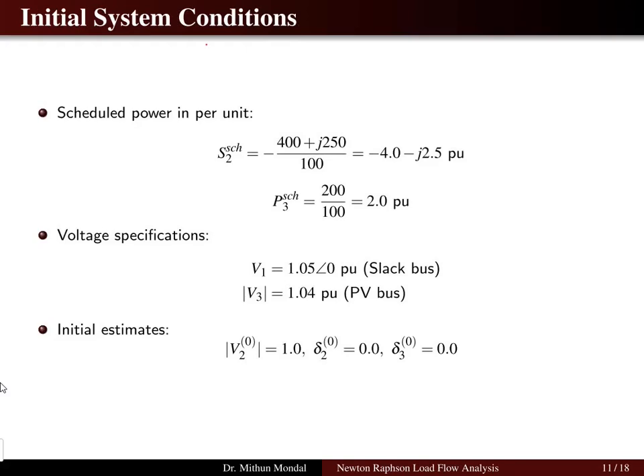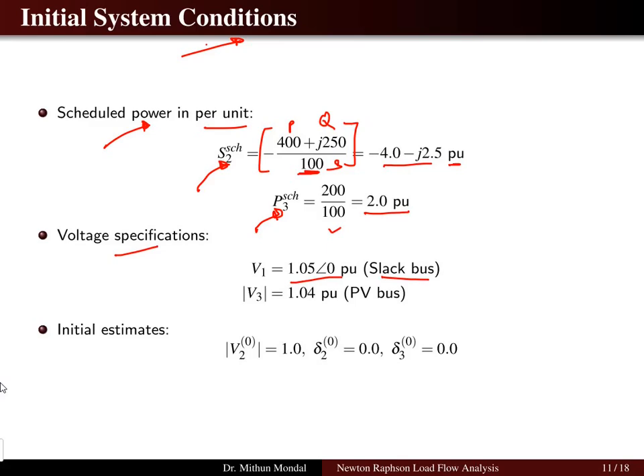The computation starts from the initial system conditions. The scheduled power in per unit for bus 2 is −400 + j250 MVA divided by the 100 MVA base, giving −4 − j2.5 per unit. The scheduled power for bus 3 is 2 per unit. The slack bus voltage is 1.05∠0°. The PV bus voltage magnitude V3 is 1.04 per unit. The initial estimates for bus 2 voltage and phase angle are 1 and 0, and bus 3 angle is 0.